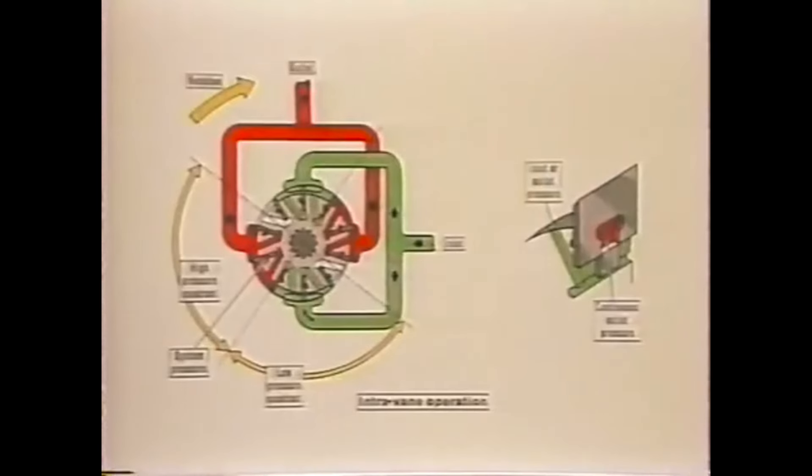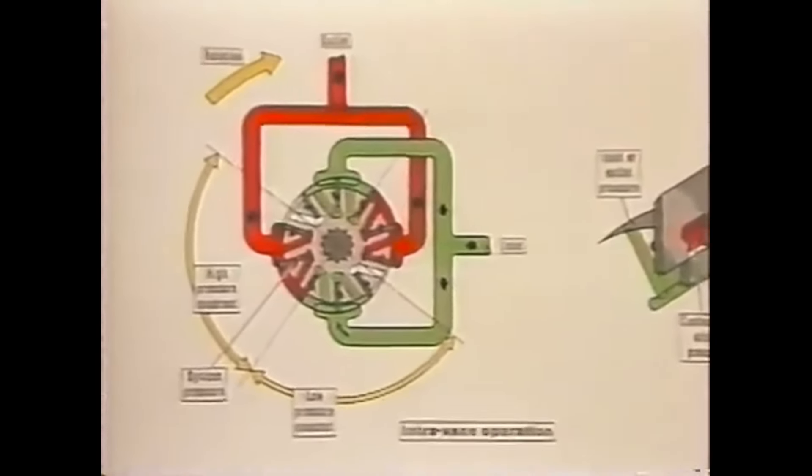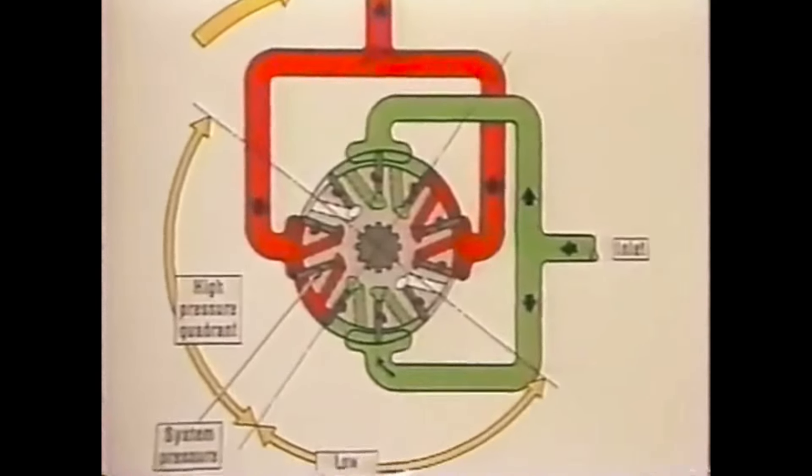Now then you'll note something different when we examine the cartridge. The two previous pumps had solid vanes and outlet pressure acted under their entire bottom surface to hold them firmly against the ring. In these pumps with their large vanes and high pressures the forces involved could reduce both ring and vane life due to high vane tip loading.